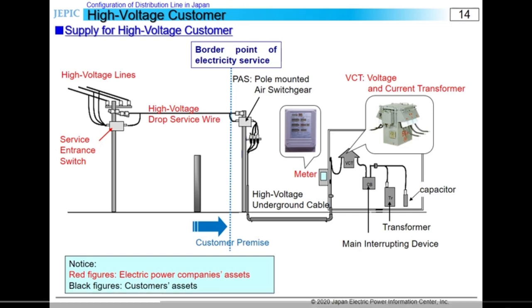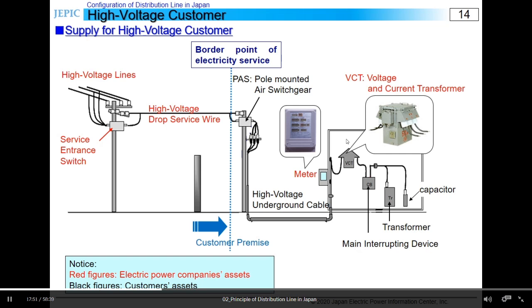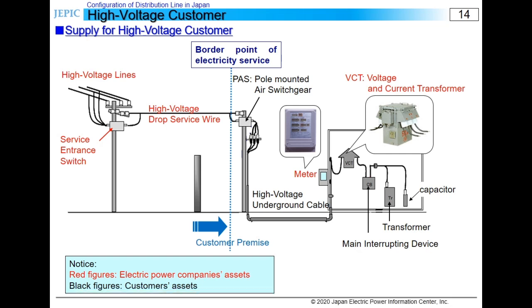Meter is installed combined with VCT on the customer side of PAS. It usually measures kilowatt-hour, kilovar, and demand. In general, a service contract of a high voltage customer is decided based on its demand, and there is a discount if they improve their lagging power factor. Most of the high voltage load is lagging, so the customers install capacitors to compensate it.